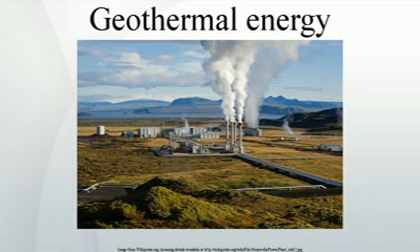Liquid-dominated plants. Liquid-dominated reservoirs, LDRs, are more common with temperatures greater than 200°C, 392°F, and are found near young volcanoes surrounding the Pacific Ocean and in rift zones and hot spots. Flash plants are the most common way to generate electricity from these sources. Pumps are generally not required, powered instead when the water turns to steam. Most wells generate 2-10 MWe. Steam is separated from liquid via cyclone separators, while the liquid is returned to the reservoir for reheating and reuse.